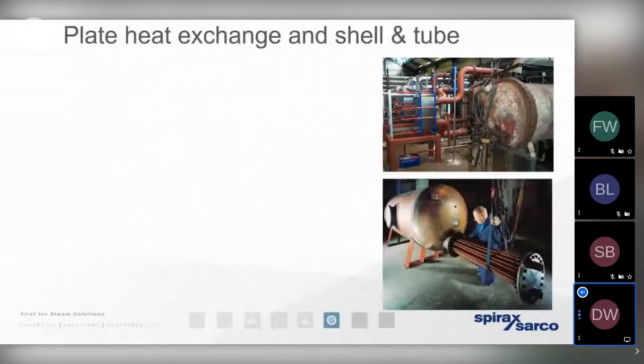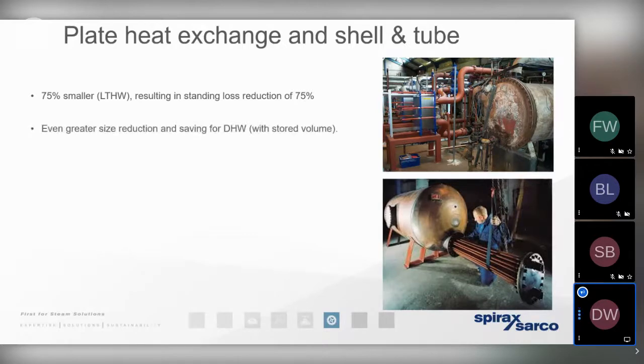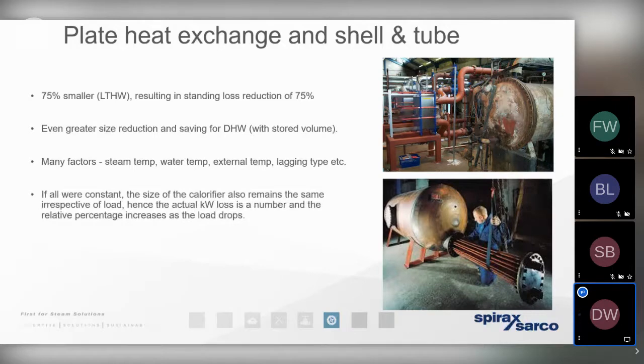And it's easy to see why so many storage heat exchangers are oversized at the design stage, because that's when it can be difficult to get accurate and reliable information from the various process owners and stakeholders around site. So if everybody was tempted to add 5% on for resilience, it means that we can generally end up with a heat exchanger that in many cases can be holding up to 3 times more hot water than the site actually requires. So you can appreciate if that were to occur, we'd get a huge footprint of space taken up by the solution in the plant room, a massive radiating loss, and a huge solution to maintain.